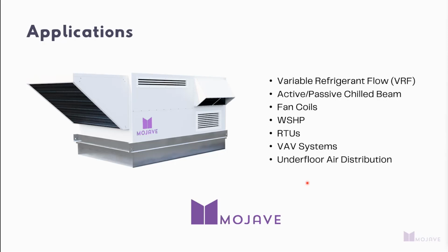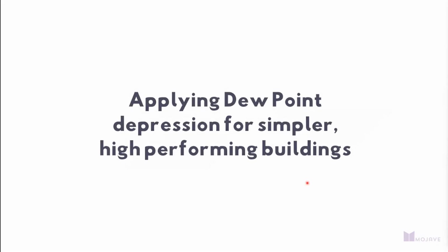So you're not just moving apples around on a table, taking load from VRF and putting it on DOAS. By leveraging liquid desiccant, you're actually shedding a portion of that load as well. So you're taking an apple off the table and downsizing your net system as a result of that as well. And then taking that a little step further, I do have an example of what a low dew point style building would look like. So let's look now at applying dew point depression for simpler and high performing buildings.